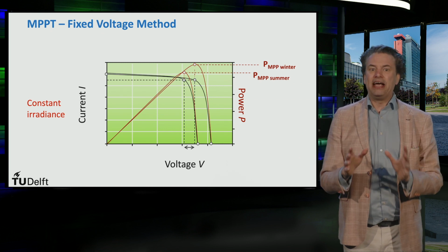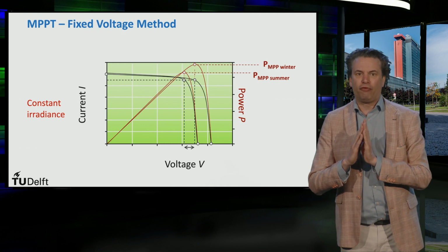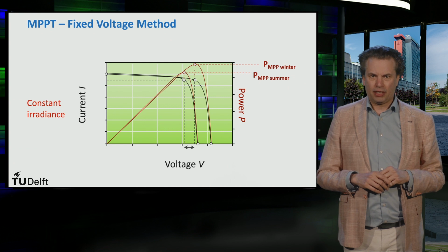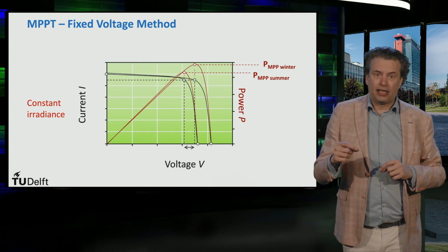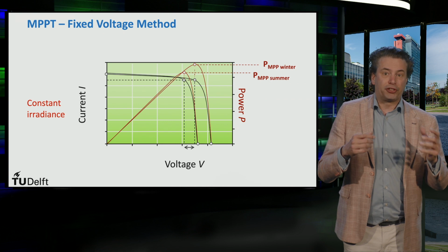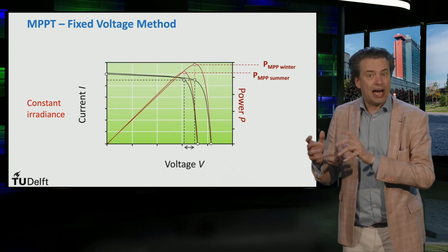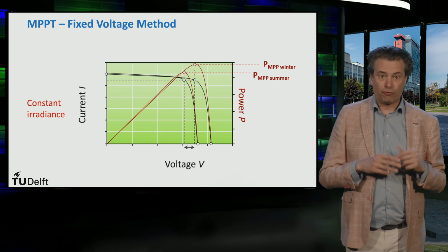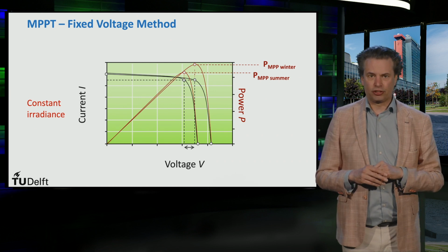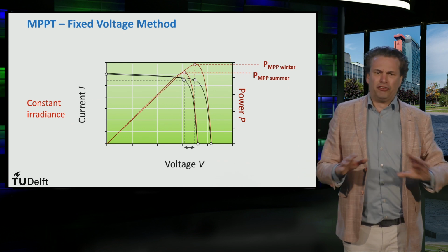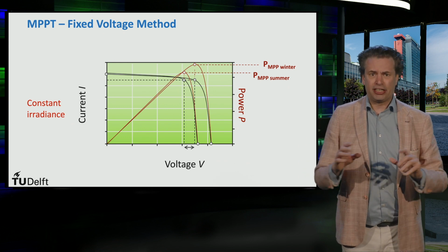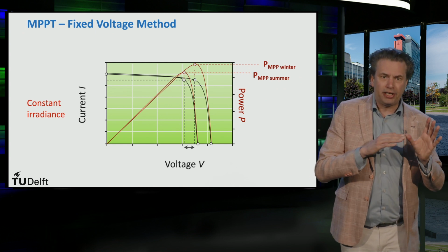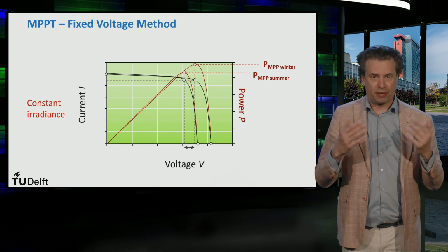This technique is based on adjusting the operating voltage of the solar module only on a seasonal basis. This is under the assumption that higher maximum power point voltages are expected during winter and lower maximum power point voltages are expected in summer, from the same level of irradiance. Of course, this method is not very accurate, and accuracy is increased if such an idea is implemented in a place with minimal irradiance fluctuations on a particular day.